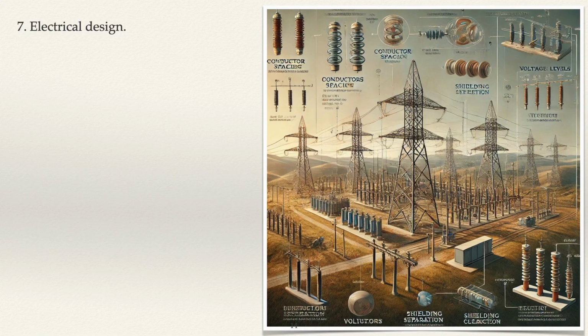2. Corona effects. The purpose is to prevent power loss, reduce noise, and minimize electromagnetic interference (EMI). Some of the explanation are: corona discharge occurs when the electric field around a conductor exceeds the breakdown strength of air, ionizing it, leads to power loss, noise, and radio interference. Design strategies: increase conductor diameter or use bundled conductors to reduce electric field intensity. Maintain adequate spacing between conductors and to the ground. Use high-quality insulators to handle high-voltage conditions. The benefits are to lower power loss, quieter operation, and reduced EMI, ensuring compliance with communication system requirements.